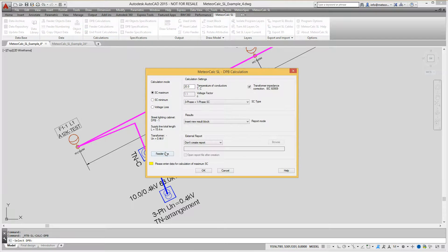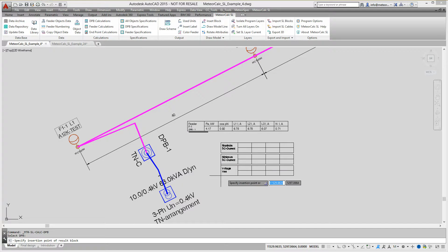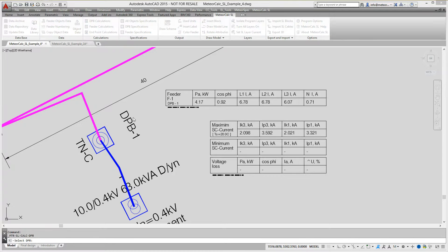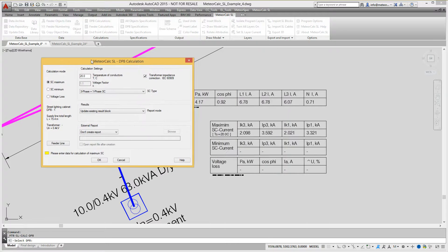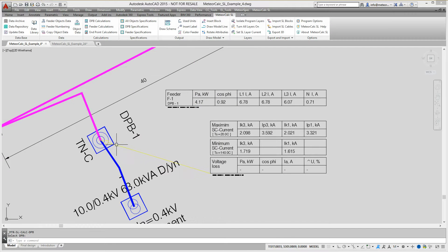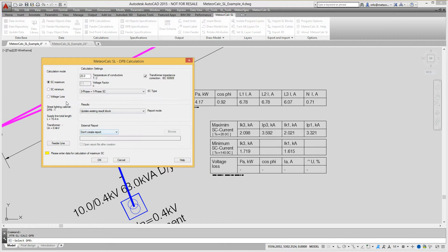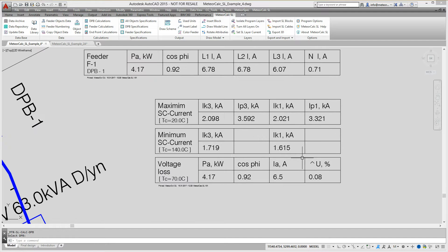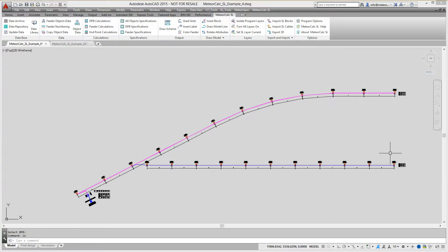Then, we perform the calculations of short-circuit currents on the main bus of the distribution panel board. The calculations for the maximum and minimum short-circuit currents are carried out separately. The calculations of power sum at the distribution panel board and voltage losses in the power supply cable from a substation are also performed separately. The results of all calculations are outputted to the common result block.